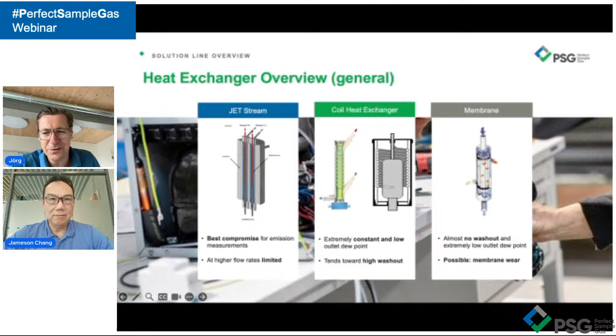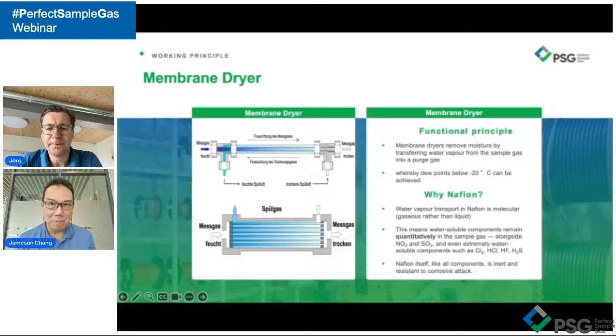Many times we have an application where we are facing high SO3. So how are we going to address the high dew point of SO3, which is an interference and also a contaminant in the measurement? In the market, basically you have two choices. Choice number one, you have a deep cooler, with a dew point of minus 20 degrees, which is going to cost you very expensive.